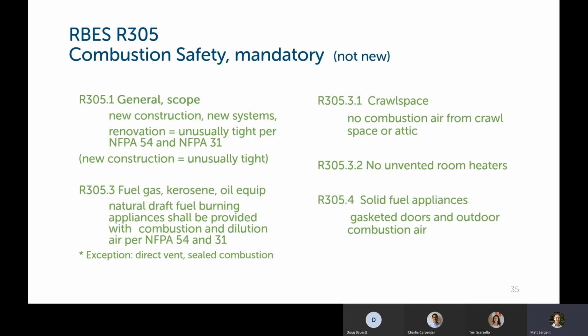So natural draft burning appliances shall be provided with combustion and dilution air. Exception is if you have a direct vent sealed combustion system, but then that's not natural draft, so it's sort of a little counterintuitive there. We can't take combustion air from a crawl space. We can't use unvented room heaters. And solid fuel appliances like wood stoves and fireplaces have to have gasketed doors and outdoor combustion air. And there's more requirements there for the closure mechanisms and things like that. So be sure you're up to snuff on this stuff.